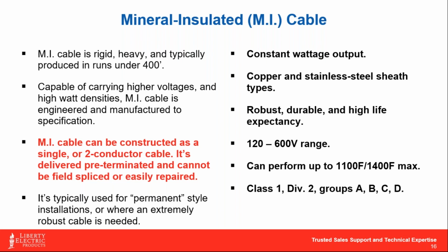This product has to be made specifically to length. It's not something that you could really splice onto out in the field. You couldn't just add, say, 10 or 15 feet of this because, hey, I'm a little bit short. This cable gets manufactured and welded to its specific length and output.